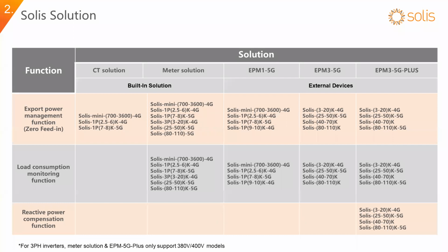All the single phase inverters we have can connect to the CT to achieve export power management, or the zero feed-in function. For other single phase inverters or three phase inverters, we can connect to the meter to do the export power management function, or we can also do the load consumption monitoring function, because with a meter we can get the necessary data to upload to the monitoring system, and then we can calculate your load consumption based on that.